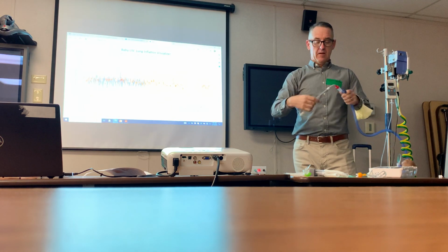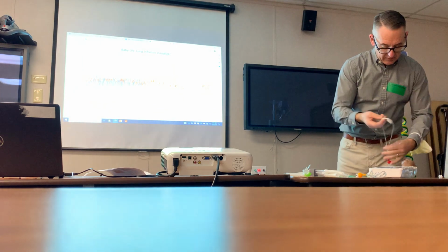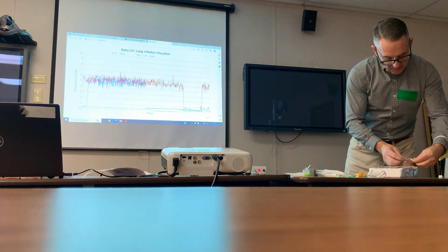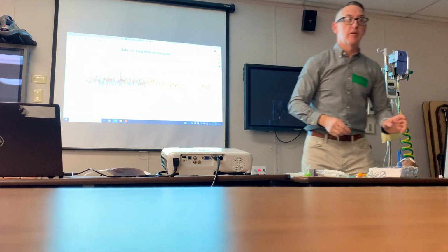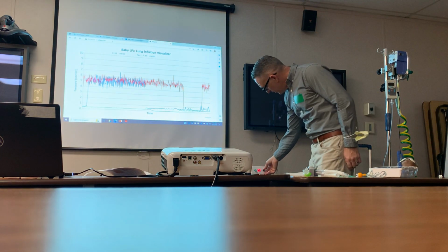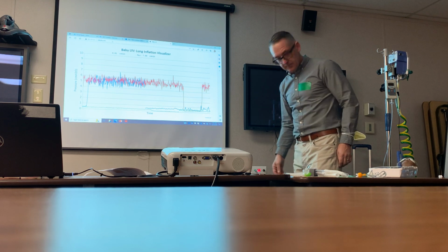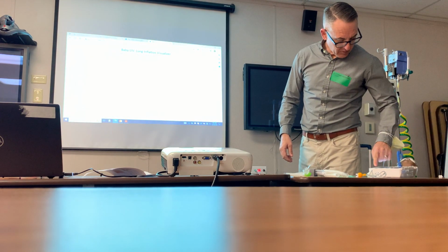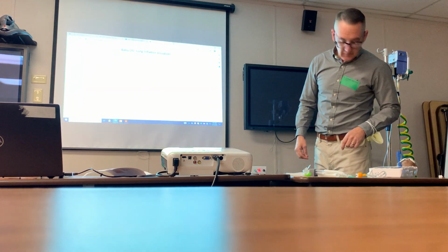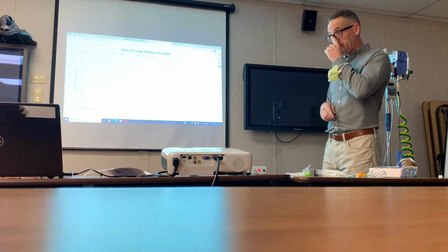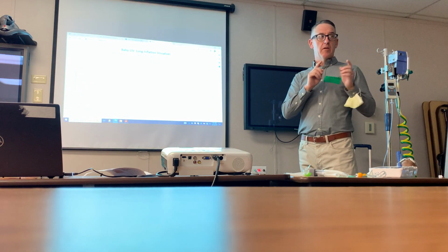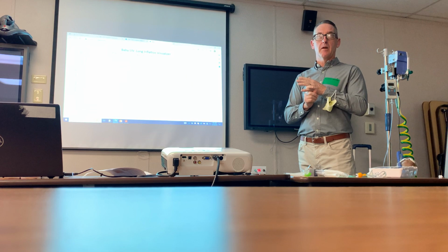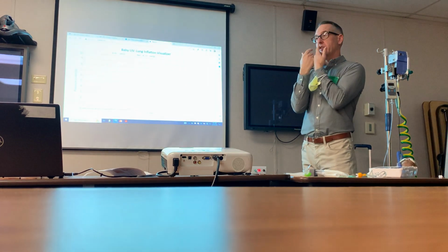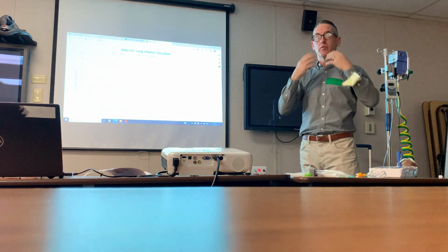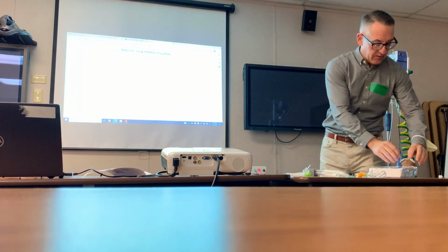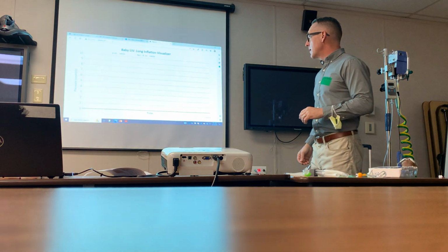What flows do you guys typically start with when you do high flow? 2 liters. If you do 2 liters, it's pretty standard in the state of California, right? So let's take a look at 2 liters. We're going to clear this, and we're going to go new. Okay, the red is 2 liters of flow. So the question is, are we meeting the inspiratory demand at 2 liters of flow? Or are the prongs becoming somewhat of an obstruction at that moment? Are they having to pull in air themselves when they're breathing at 2 liters? So in the studies, remember, we wanted to get to at least a minimum of 4 liters of flow.